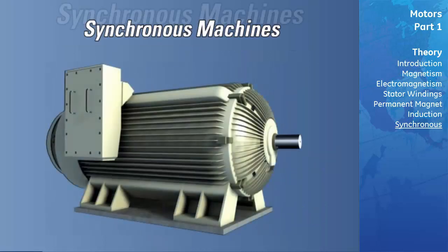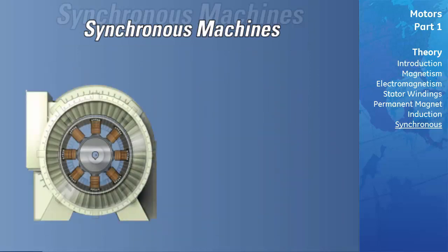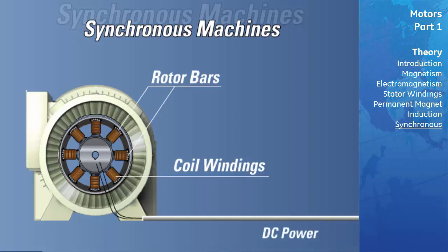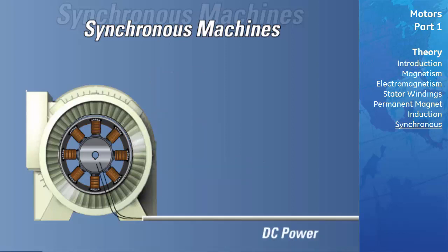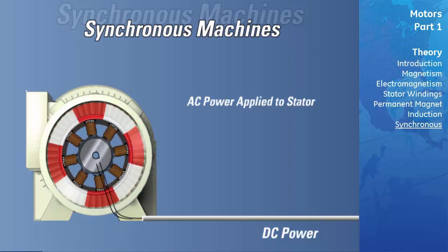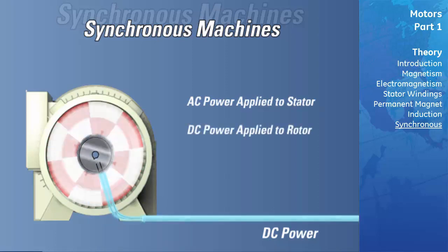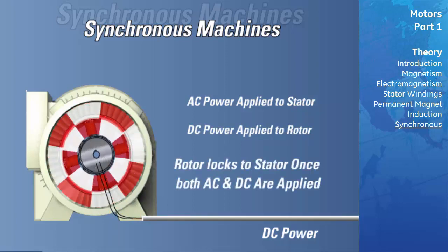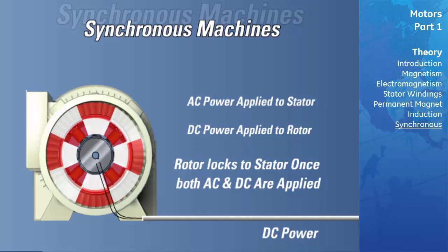Larger motors tend to be synchronous machines. The rotor of the synchronous motor is constructed similar to that of the squirrel cage rotor, but in addition to rotor bars, coil windings are added. These coil windings are connected to an external DC power source through a slip ring and brush assembly. During a start, AC is applied to the stator and the motor accelerates as an induction motor would. Once it reaches maximum speed, DC is applied to the rotor coils, producing a strong, constant magnetic field in the rotor. This field locks in step with the rotating stator field, and there is no difference in speed between the rotor and the stator's rotating field.